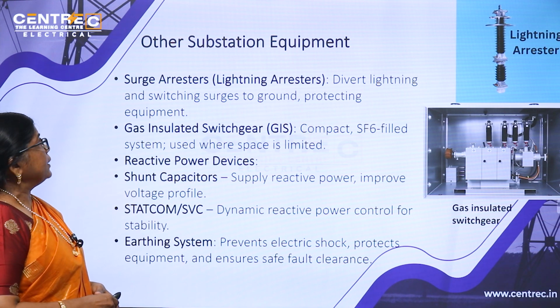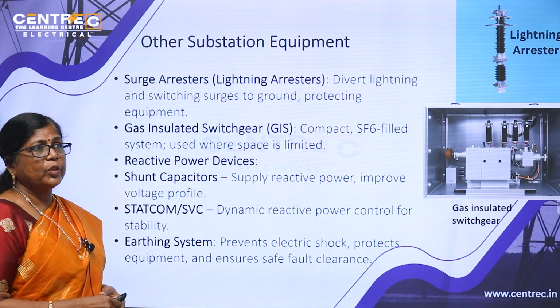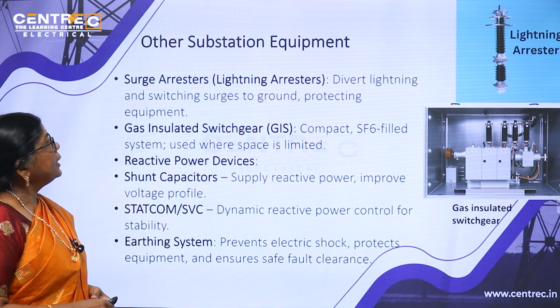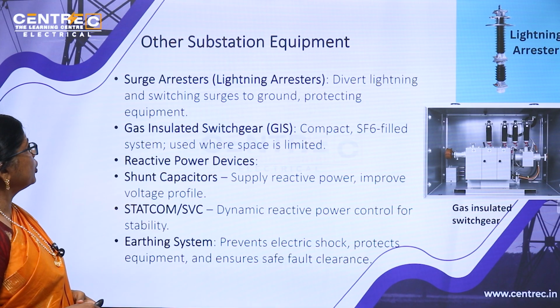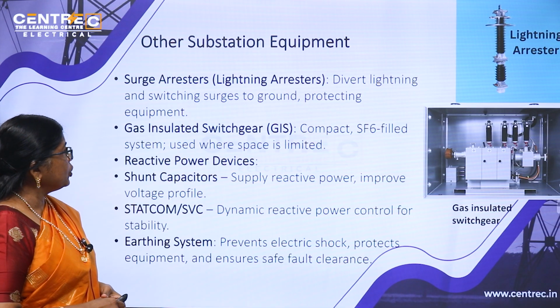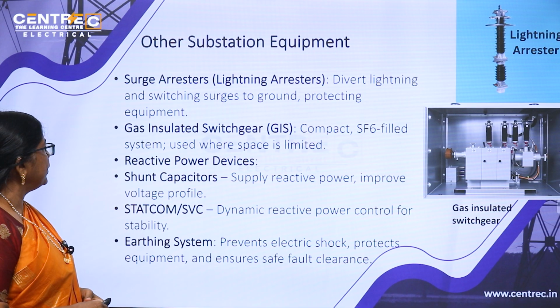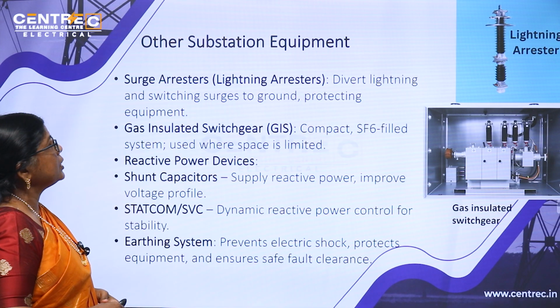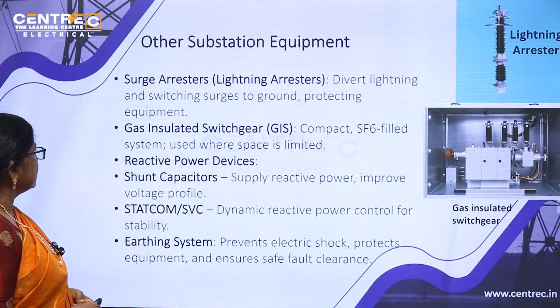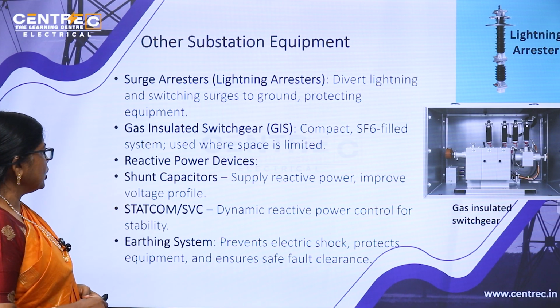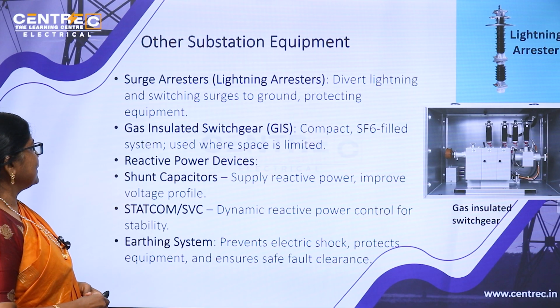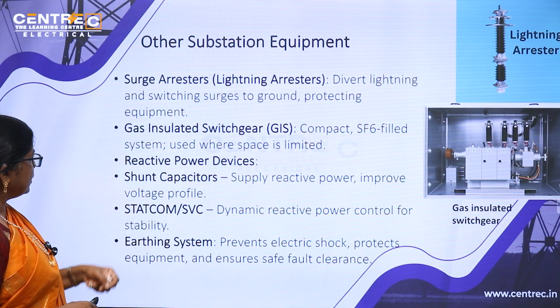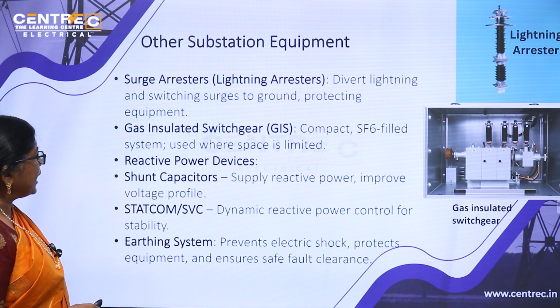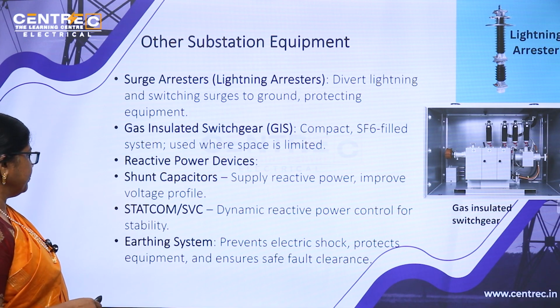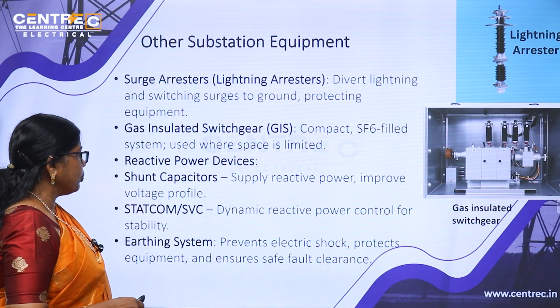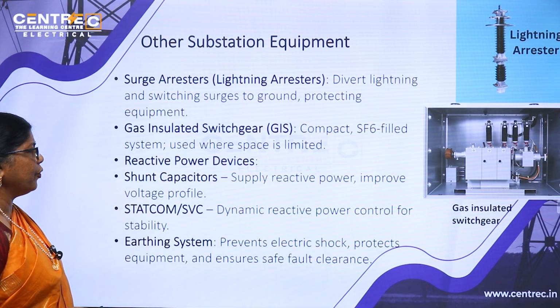Other substation equipment: surge arresters, or otherwise we call them lightning arresters, divert lightning and switching surges to ground, protecting equipment. Then gas insulated switchgear, a compact SF6 filled system, used where space is limited. Reactive power devices are shunt capacitors and STATCOMs, that is static. Shunt capacitors supply reactive power and improve voltage profile. STATCOM or SVC, dynamic reactive power control for stability. Earthing system prevents electric shock, protects equipment and ensures safe fault clearances.